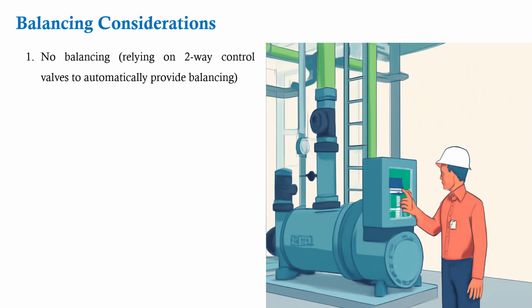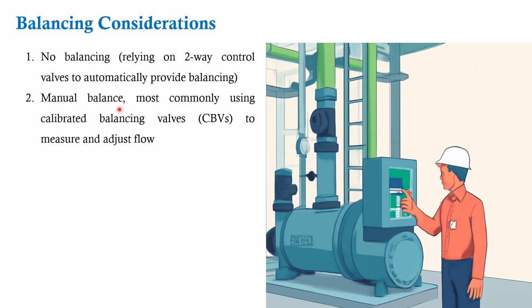So the first point is if people have no balancing valve in the equipment itself and are only relying on the two-way control valve. This two-way control valve is not balancing actually. It's just controlling, regulating the flow. So if it is the case, how is it going to impact? So this is one of the strategies. Second is the manual balancing valve.